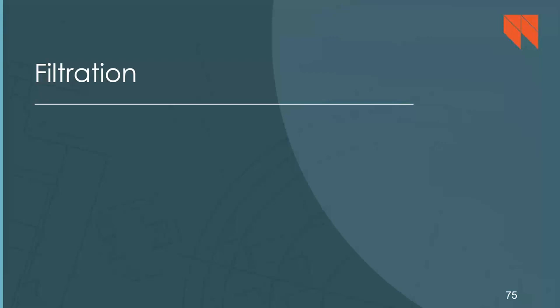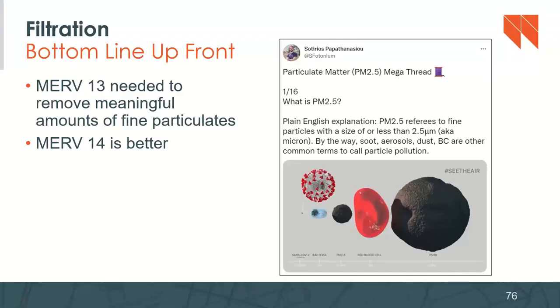We're going to move on to filtration. These last couple of slides are the last couple of slides we've got for the talk, and we're getting close to that time, but we wanted to talk a little bit about filtration. While filtration is not necessarily part of every ventilation system, right? Like an exhaust only system, you're not going to get filtered air. A supply only system, you might. There are some products out there where the supply air is going to move through a filter before it enters the space. But on almost all ERVs and HRVs, there is filtration. And so I wanted to talk about filtration a little bit.